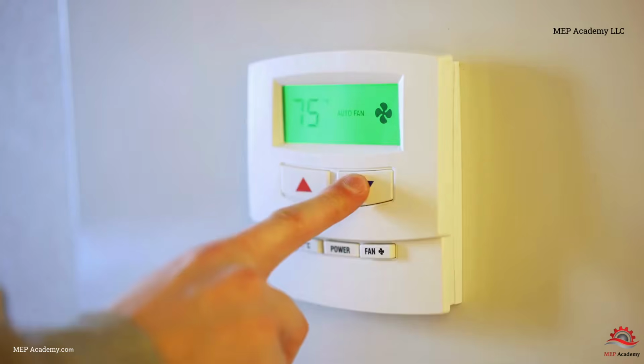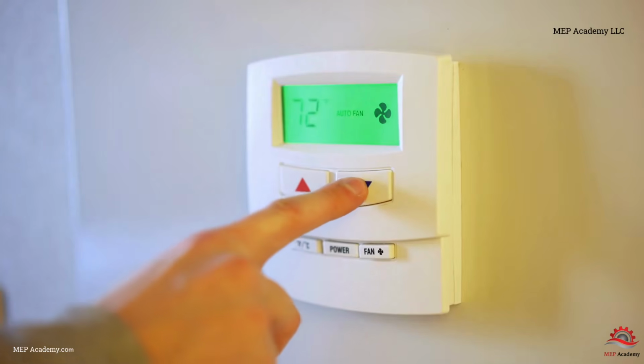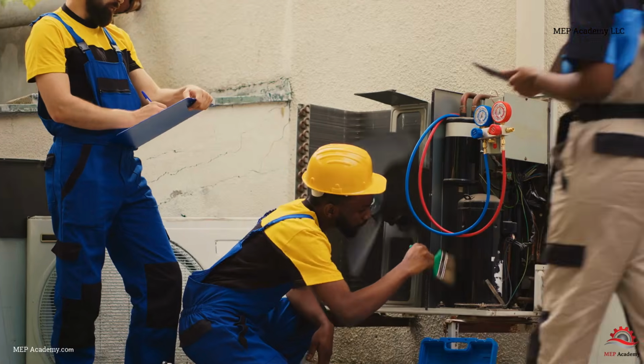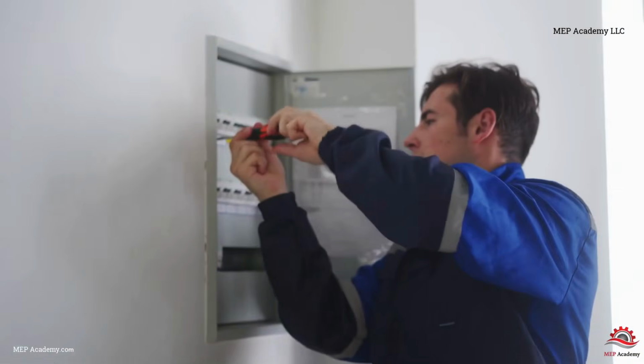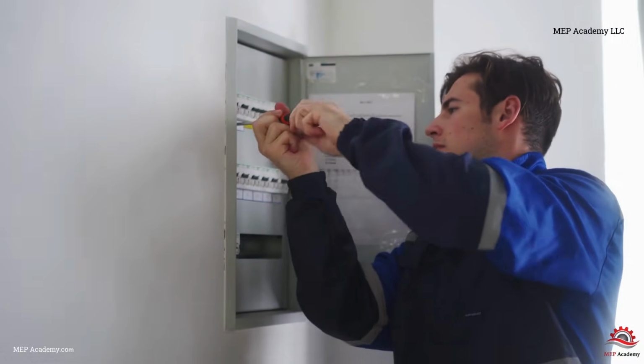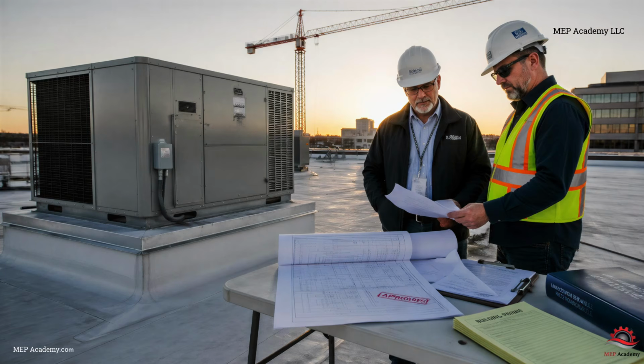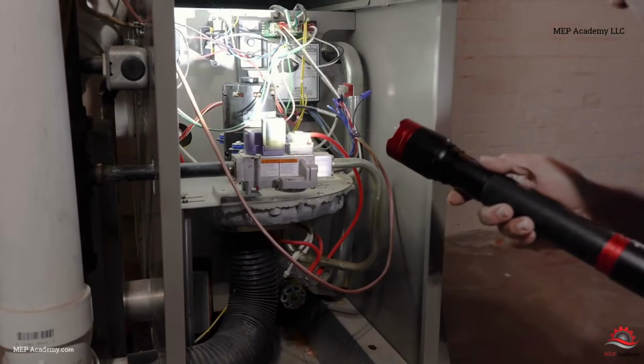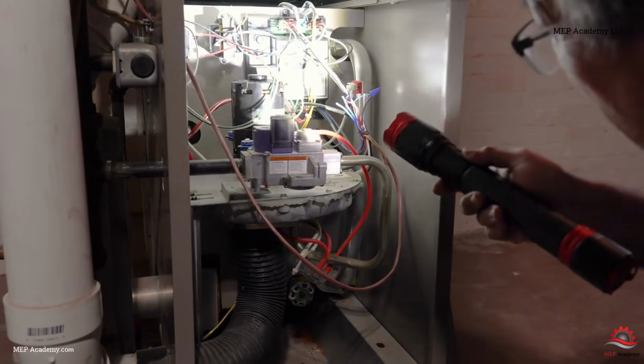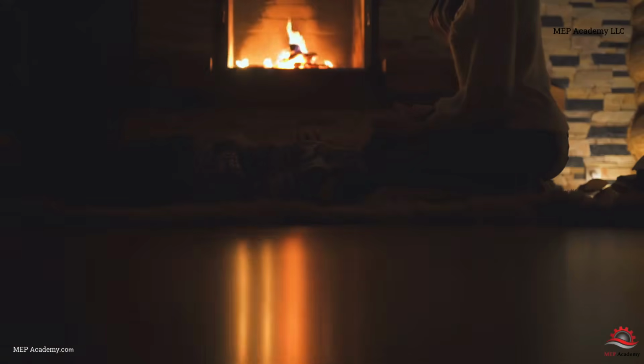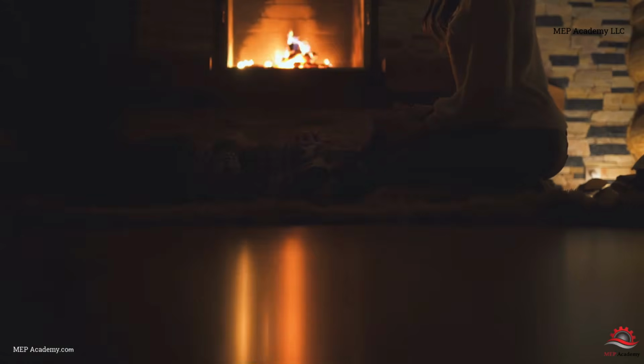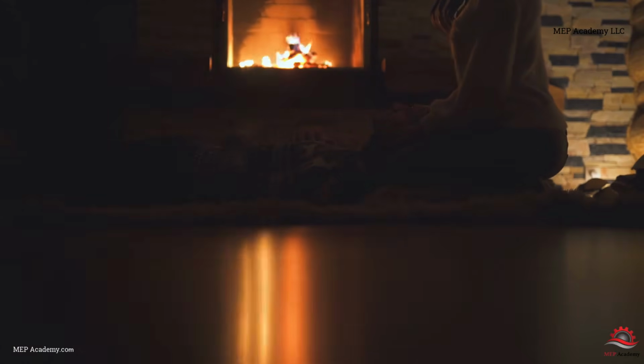Common causes include oversized equipment, faulty thermostats, refrigerant issues, control problems, dirty coils, restricted airflow, or safety devices that repeatedly trip and reset. Short cycling creates several secondary problems. Humidity removal decreases. Energy consumption increases. Comfort becomes inconsistent. Equipment life expectancy is reduced.